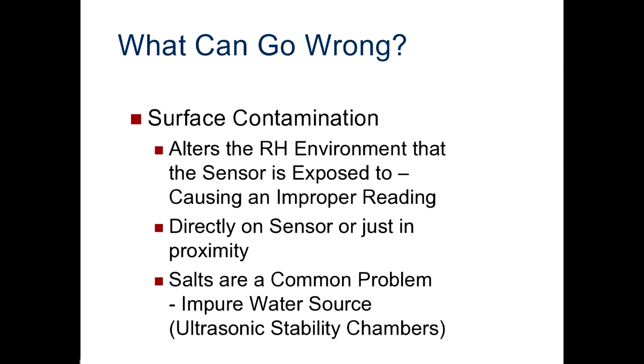Sometimes contamination can be directly on the sensor, or sometimes it can even be near it or on its enclosure or probe body. Salts are a common source of this problem, and an impure water source may be the source of them. This can occur with ultrasonic stability chambers, for example, when the water is splashed around the chamber and onto the sensor, causing an error in the measurement.